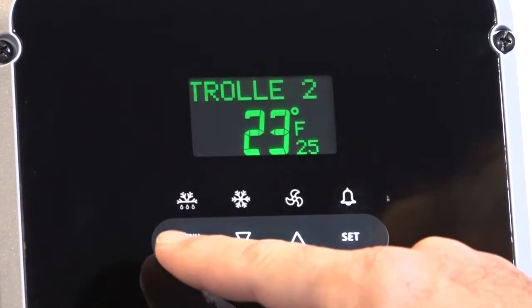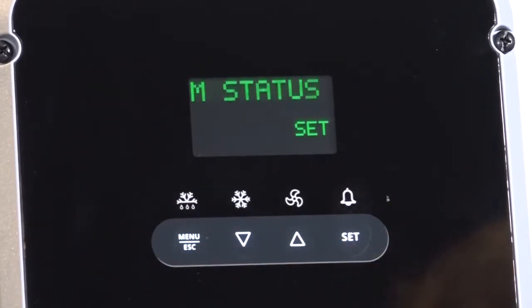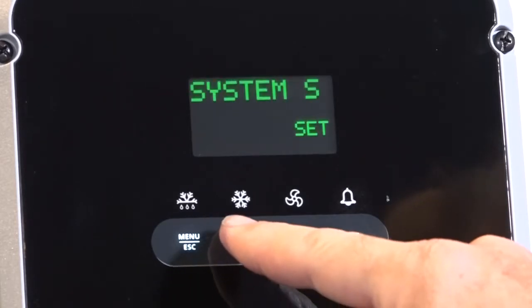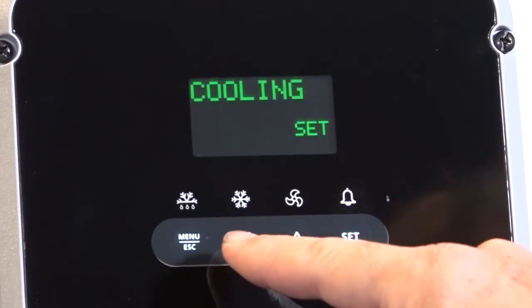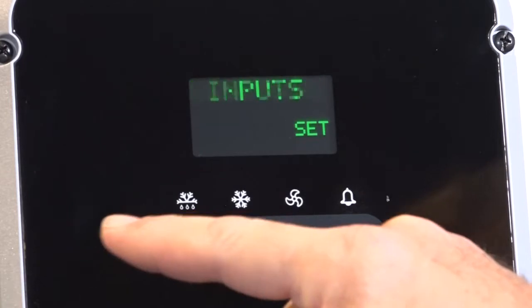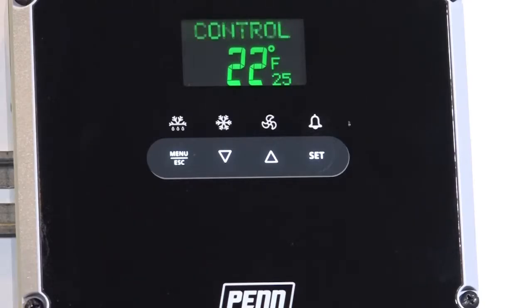The display of the A525 is quite unique. It combines a dot matrix messaging area with a large 4-character area for time and temperature. The dot matrix messaging area provides for programming simplicity. Every programmable function is described in plain language. This allows the user to understand the information that needs to be programmed without referring to a user manual. The main display features the current space temperature as well as time and date information during programming. There are 2 smaller dot matrix areas that also are used for providing additional information for programming simplicity.